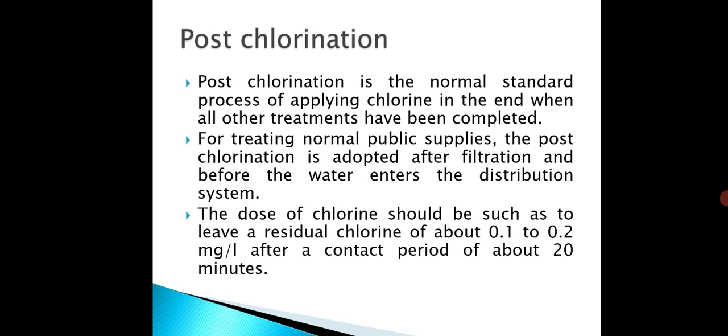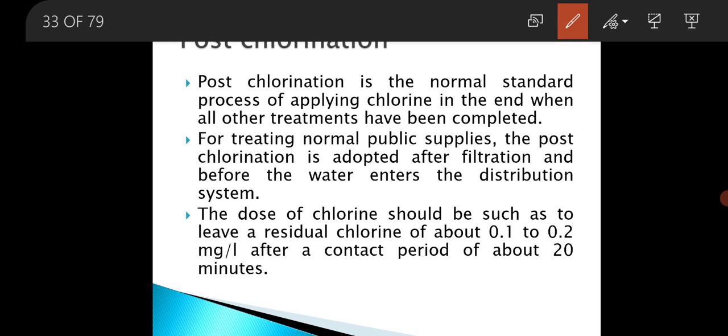Next is post-chlorination. Post-chlorination is sometimes simply called chlorination, and it is the normal standard process of applying chlorine in the end when all other treatments have been completed. While treating normal public supplies, post-chlorination is adopted after filtration and before the water enters the distribution system.